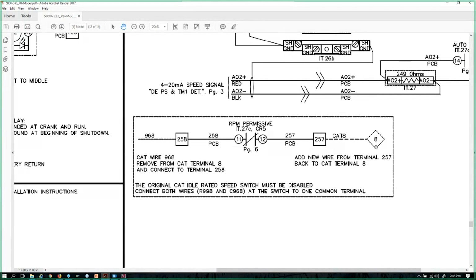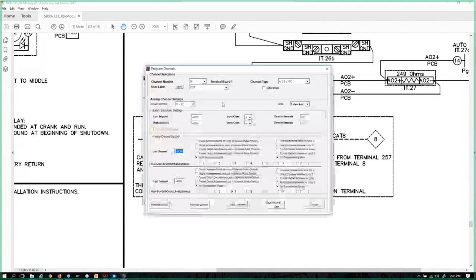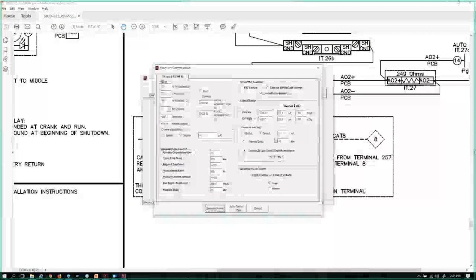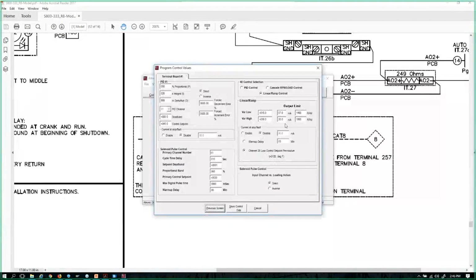As long as I ground this circuit on this particular engine, the engine will hold at what we call an idle speed. So with knowing that, and knowing how we might have built the panel, I could say, well, at 80 degrees Fahrenheit, turn on digital output 3 so we can unground Cat terminal 8 and allow it to go to rated speed. But then, at the same time, I could keep my low control set point, which is going to act as a high set point for what I'm showing you, at 120, to where it's going to prevent the auto control speed from being able to work correctly until we hit 120 degrees.